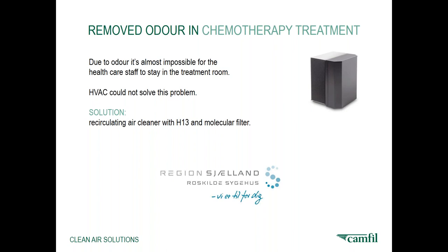After analyzing the complex mix of substances of liquid which was flushed into the patient and generates the odor, we selected the perfect combination of molecular media to adsorb the gas molecules that generate the smell. The solution was just a recirculating air cleaner with molecular and H13 filter. And keep in mind, the patient themselves does not smell this odor. It's for the nurses and the staff.